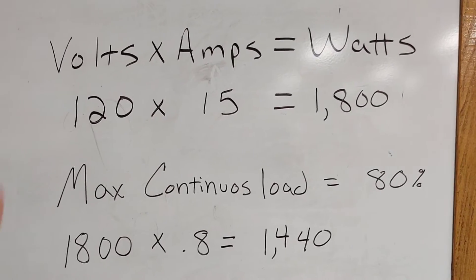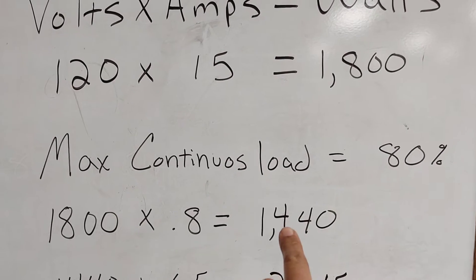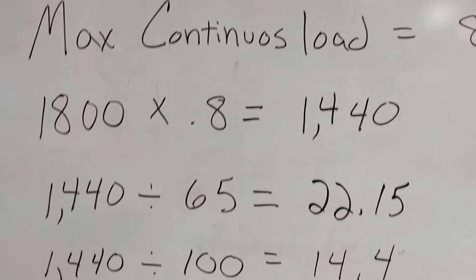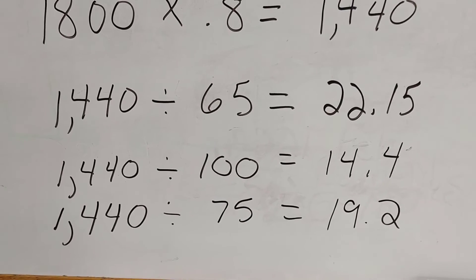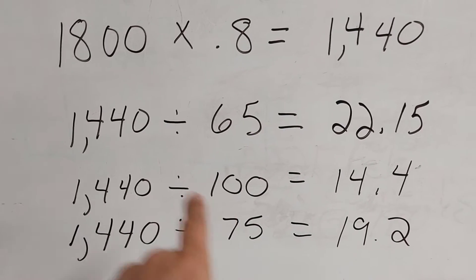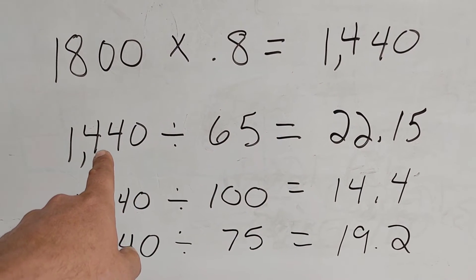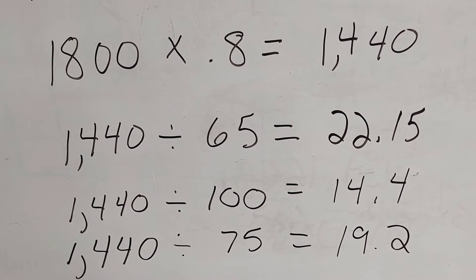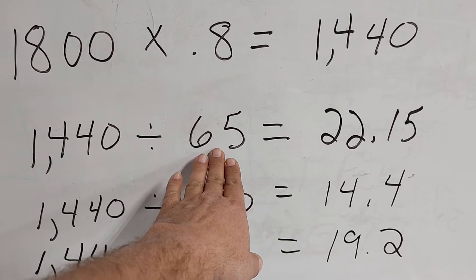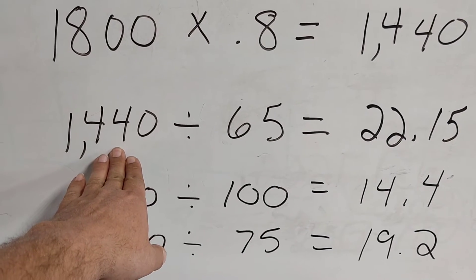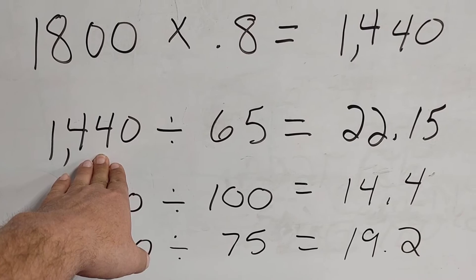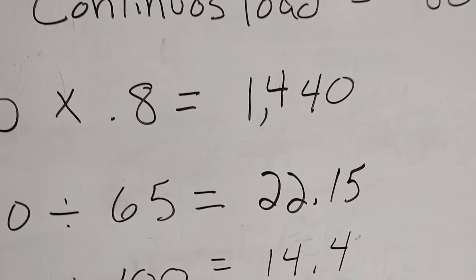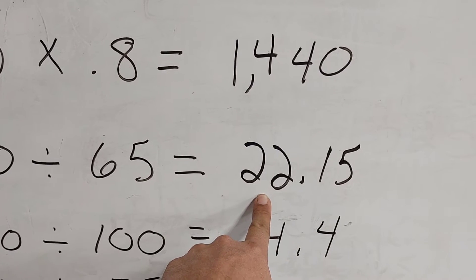I have our 1,440 watts divided by 65 watts—we're dividing the wattage of the fixture by the actual wattage that we're allowed to use on a 15 amp circuit—and we come up with a total of 22 fixtures. But now say you are using a fixture that's rated for 100 watts. You're going to divide 1,440 by 100 watts, and you're going to be able to put 14 fixtures on that 15 amp circuit.